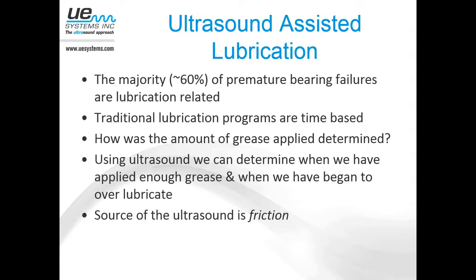We've put a one-two punch to it, and we've been able to realize a tremendous amount of success where we'll identify which bearings need to be lubricated through our regular condition monitoring route, and then we'll optimize the procedure for lubricating that bearing by going out with one of our ultrasonic detectors that mounts right on the grease gun to ensure that you're not putting too much in. So it's a real-time lubrication process where this one needs it, this is how much we're going to put in, no more.